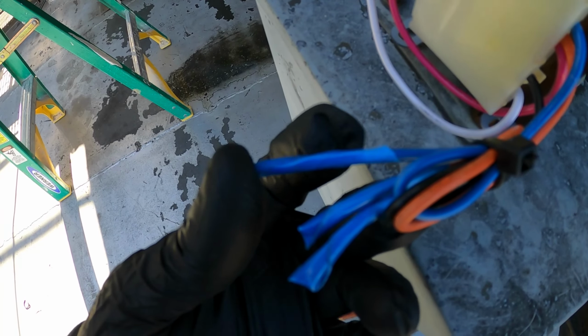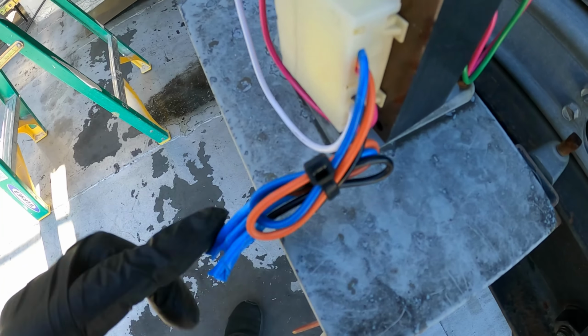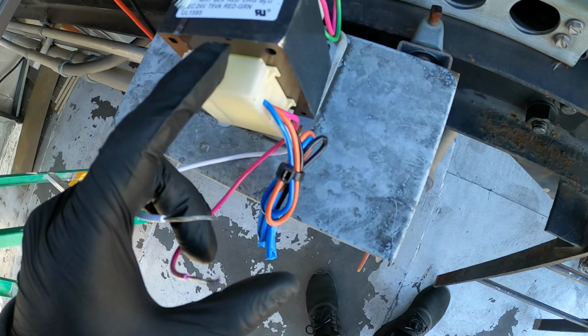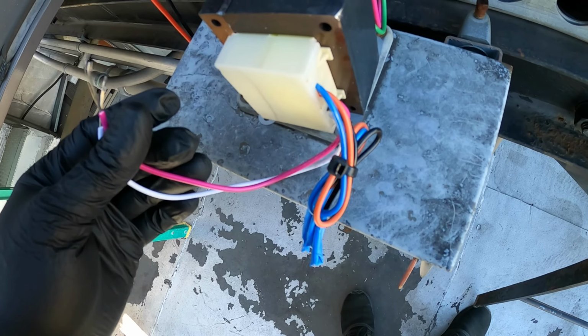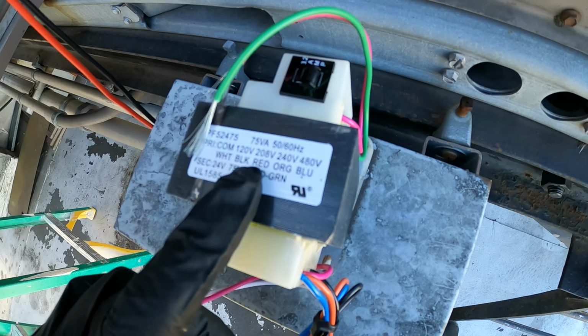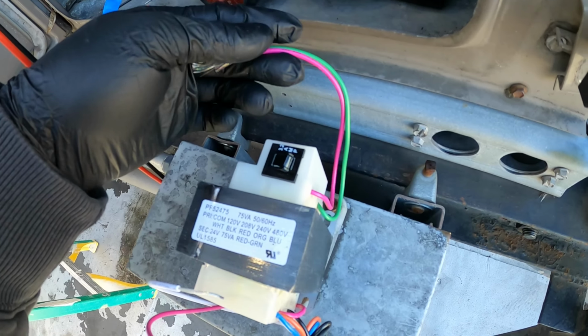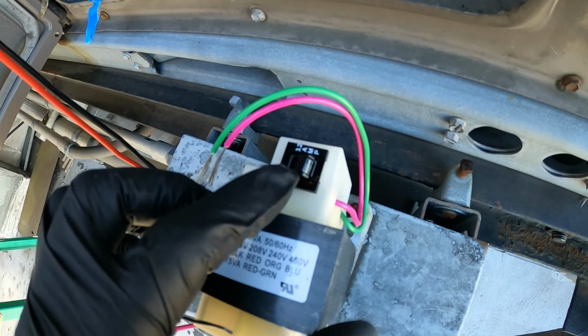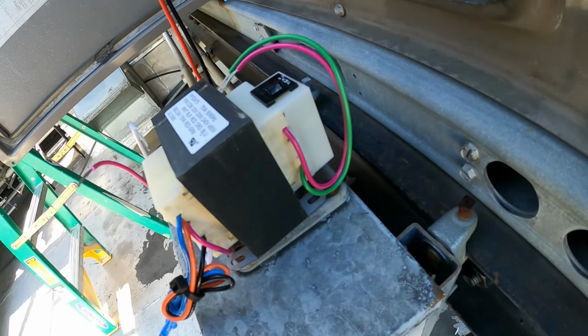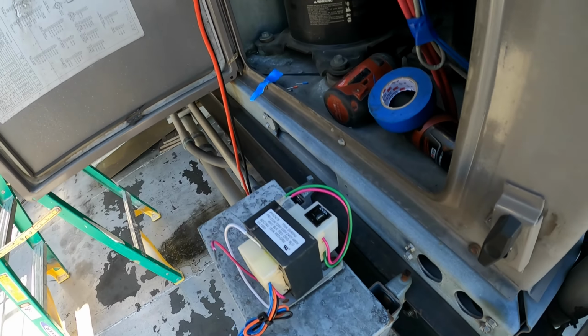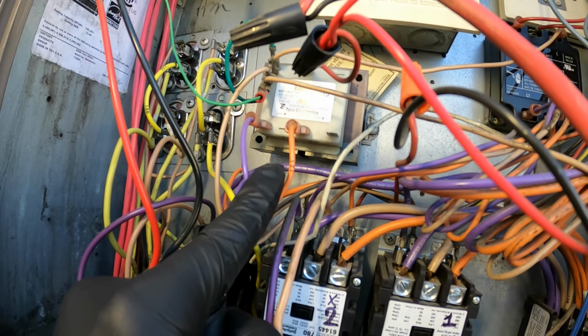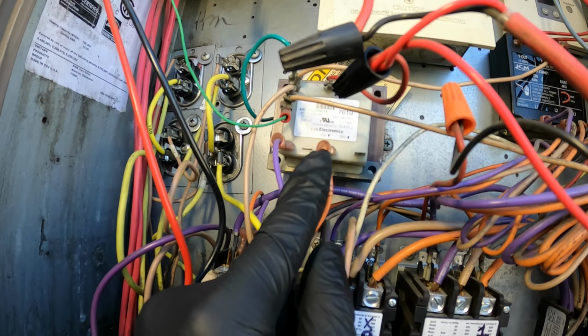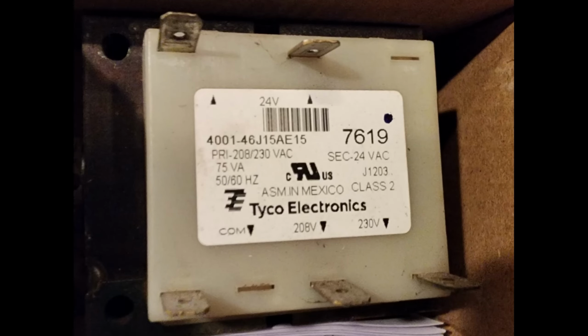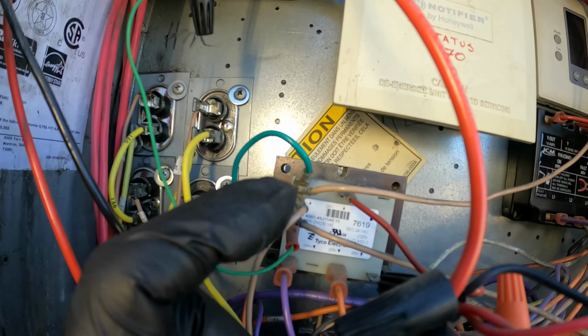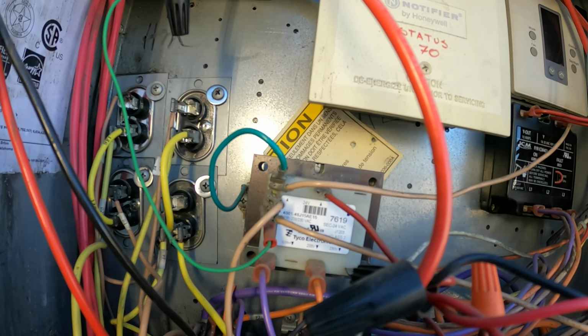All right, so I taped off each line individually that I'm not using, put a tie wrap just to kind of separate it. So this side where we have all the wires is going to be our primary. As you can see, we have all those options here, and these two are going to be our secondary, also because you have the breaker on that side as well. Primary, secondary. On this one, this is the primary because it says 208 volts. I'll show you guys a picture. And this side is a secondary because this says 24 volts.